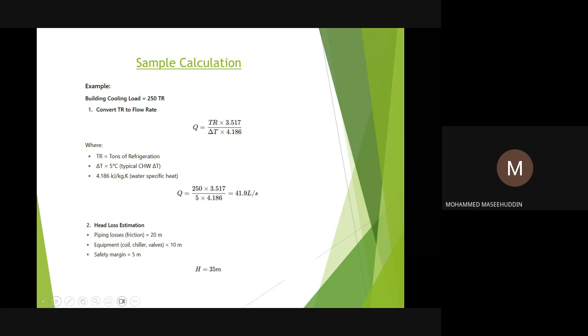Okay, here's a typical calculation for the flow rate and head from the chiller itself, because it's a chilled water system. So let's say we have a chiller of 250 ton. Using this formula, Q flow rate is equal to tonnage times 3.517 divided by delta T, which is normally taken as 5 degrees centigrade in chilled water systems, times 4.186. This will give us the flow rate, which has come to about 41.9 liters per second.